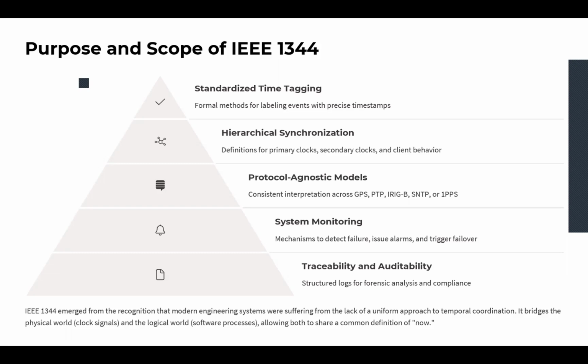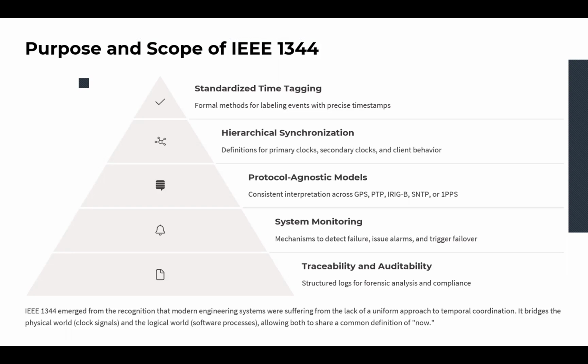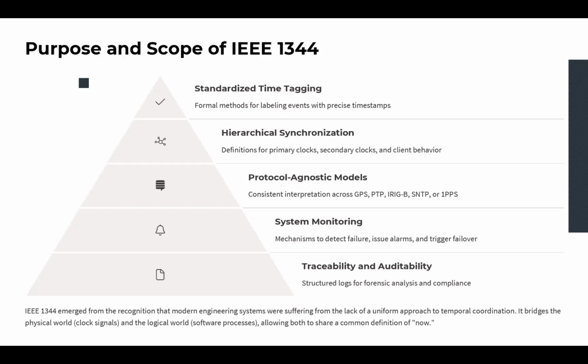Let's break down the five important pillars that exist in this standard. One is that we have to make sure the time tagging is standard. What that means is that this standard defines how we have to label every critical event or measurement, or when we send a control signal. And how we tag that event should be a precise and traceable timestamp. That part includes format, resolution, and even reference and associated quality metadata of that time tagging.